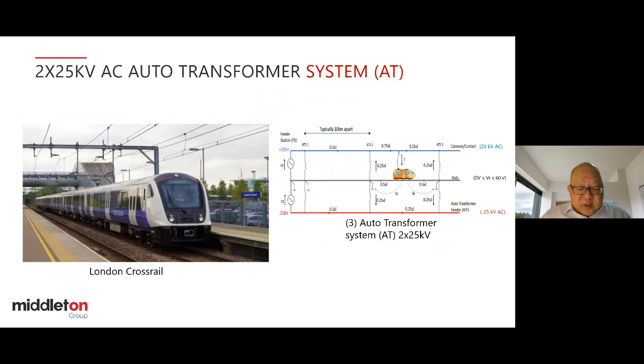This is an auto transformer, or the AT system. The AT system distributes power at 50 kV, but the train draws power at 25 kV between the contact wire and rails. There's also an additional conductor called the auto transformer feeder, ATF for short, and in France it's called the negative feeder. ATs are installed typically at 10 kilometers apart along the lines, and they connect the positive 25 kV and minus 25 kV, and the midpoint, the center point, is connected to earth and to rails.